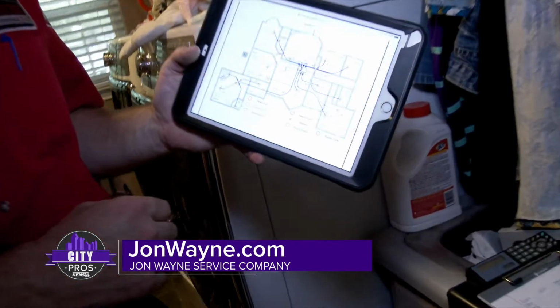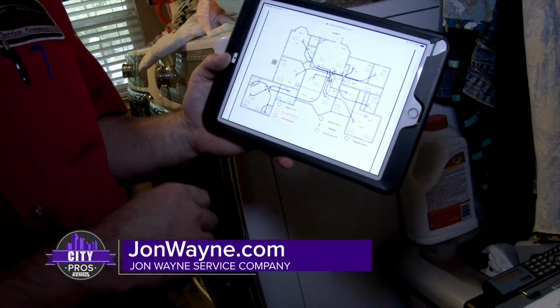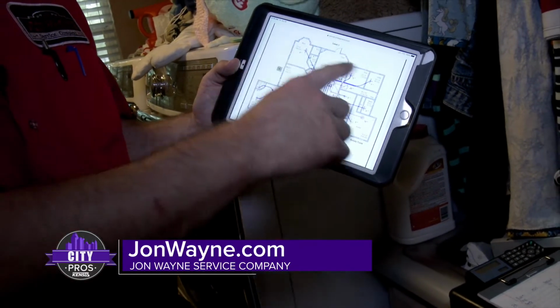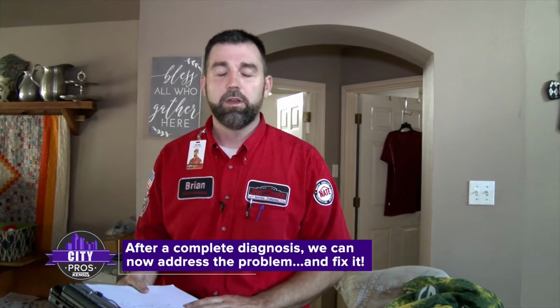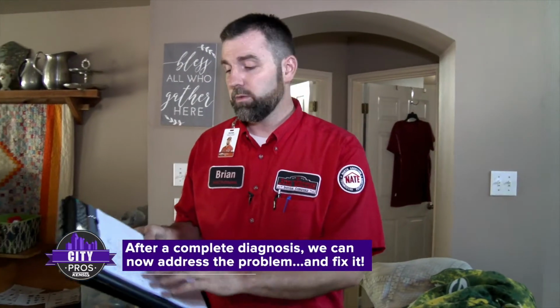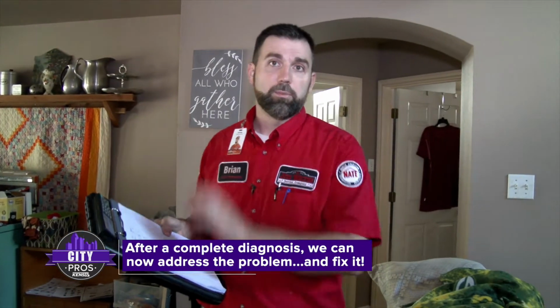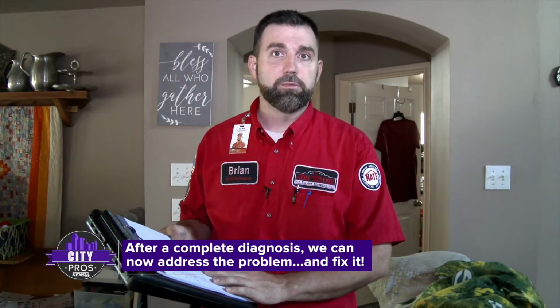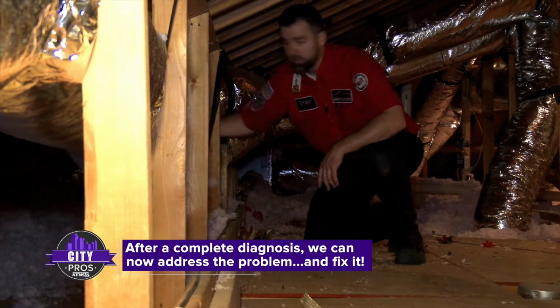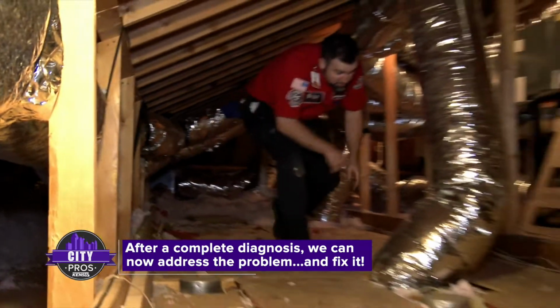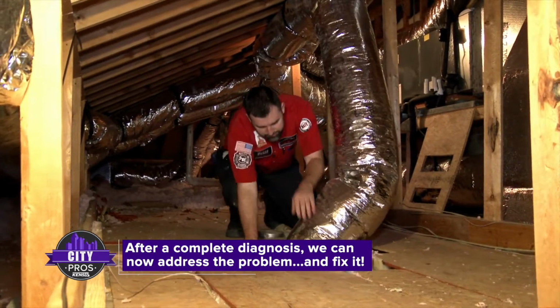So this is a room by room drawing of our house. It has all of the ductwork, where the unit is located, and each room individually. Now that we've measured every room and taken a look at the numbers, we found an imbalance in our problem room. We need to put more air in that room. So the next step is making some adjustments to the ductwork and some of the dampers to get more airflow in that room.